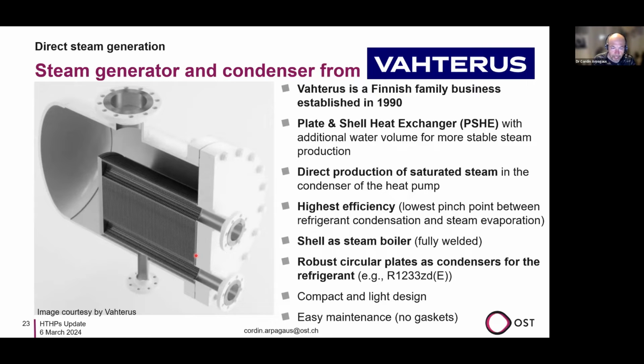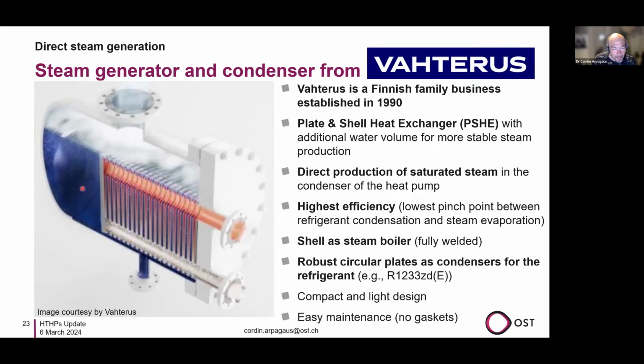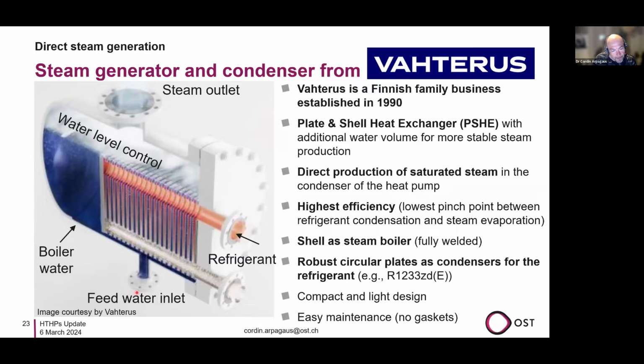These are so-called plate and shell heat exchangers, and they have an additional water tank here on the left to stabilize the steam production. So here we have it in a color visualization. We have here the water that is fed into this heat exchanger from the bottom. Then we have the refrigerant, which would be, for example, the R1233ZD, this HCFO, which is the hot part. It gives the heat to the water, evaporates the water in the tank, or in this shell of the heat exchanger, and the steam is generated here on top, which leaves the heat exchanger.